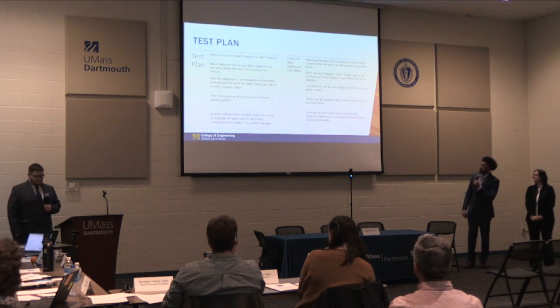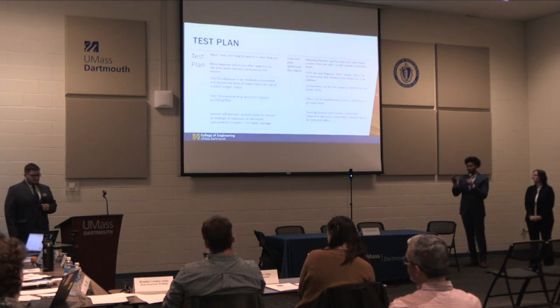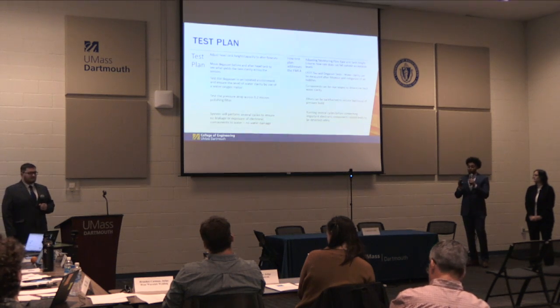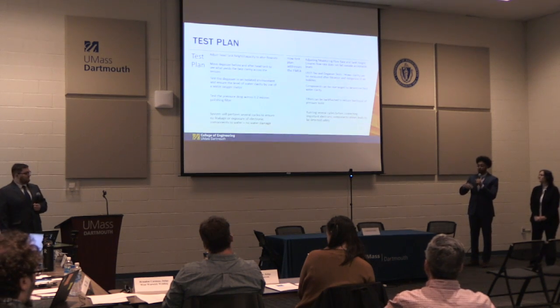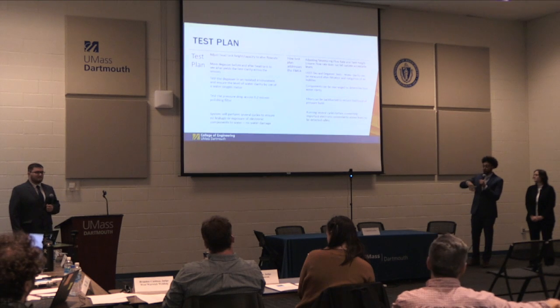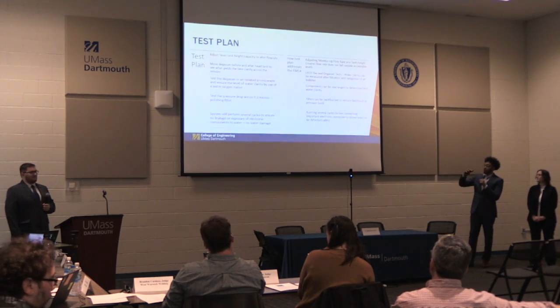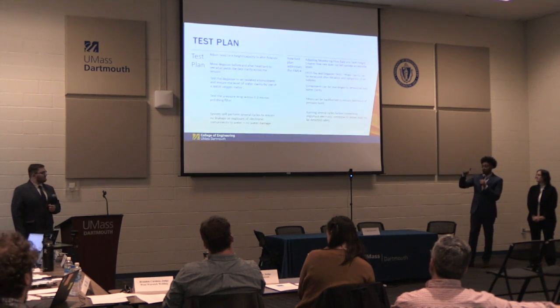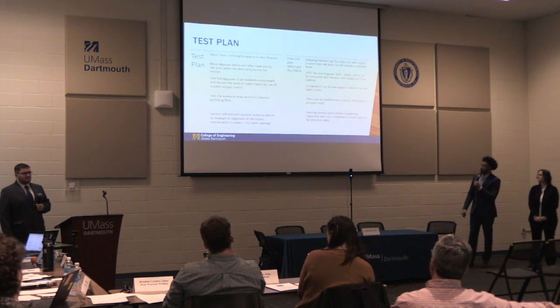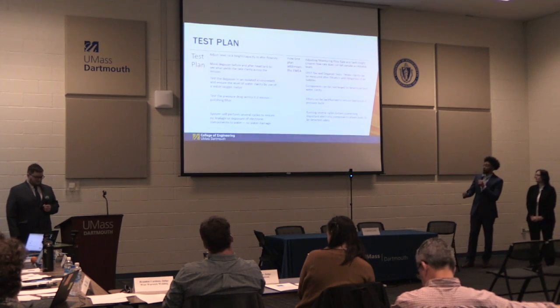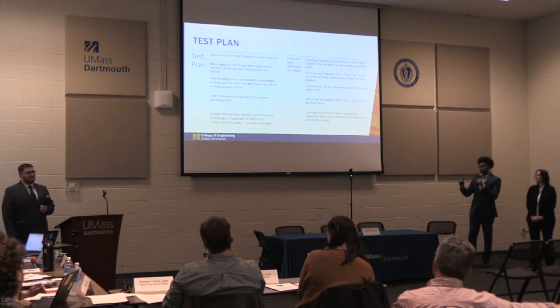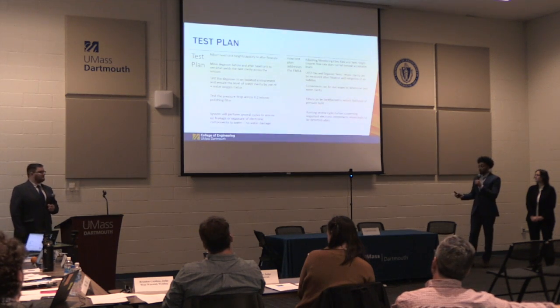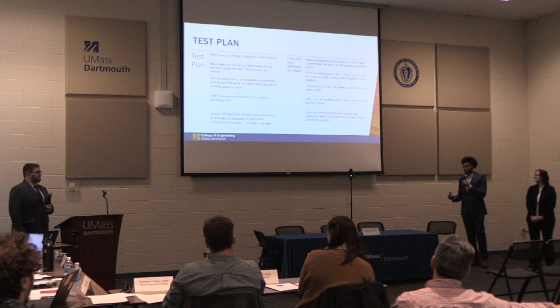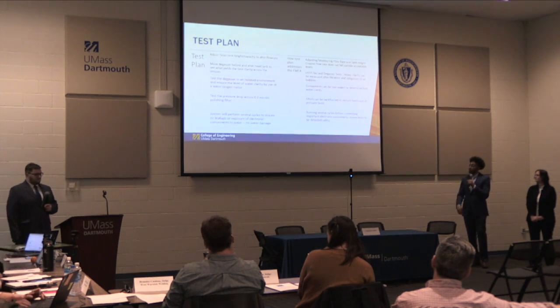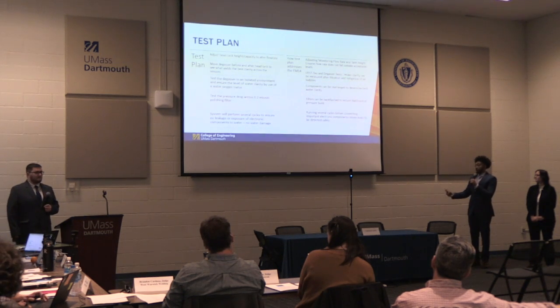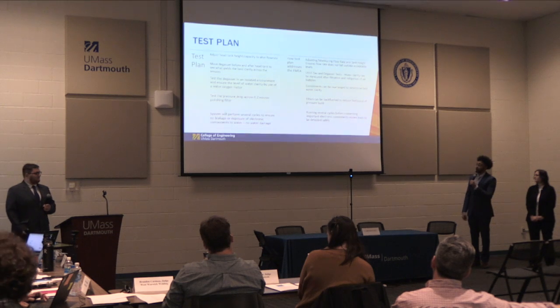Furthermore, we looked into moving the degasser module before and after the head tank. Using the degasser before the head tank allows us to use the pressure gradient across the filtration line and the pump to get the water degassed and pull vacuum on the degasser module. We weren't able to have the degasser module after the head tank and flow into the sensors. This would have been optimal to create 0 air bubbles going through the water into the sensors, but we would have to purchase another pump in order to create the flow.